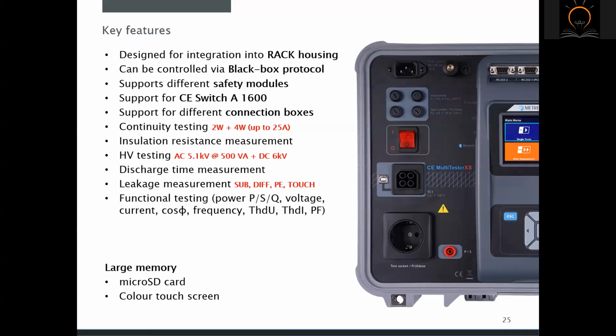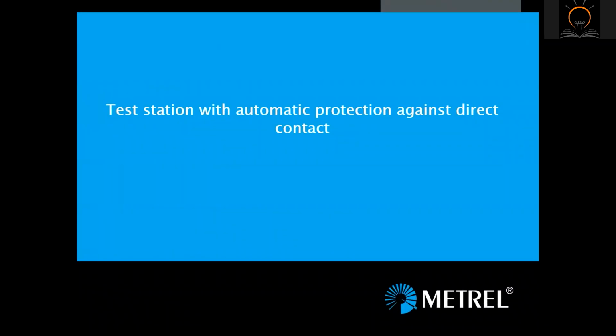It supports insulation resistance measurement, high voltage testing with both AC and DC voltages, discharge time measurement, different leakage measurements including substitute leakage, differential leakage, PE leakage and touch leakage, and functional testing for single-phase appliances. The instrument supports large memory with micro SD card and, of course, touch screen. All active and passive components presented in the previous slides can be easily integrated into the entire test system.